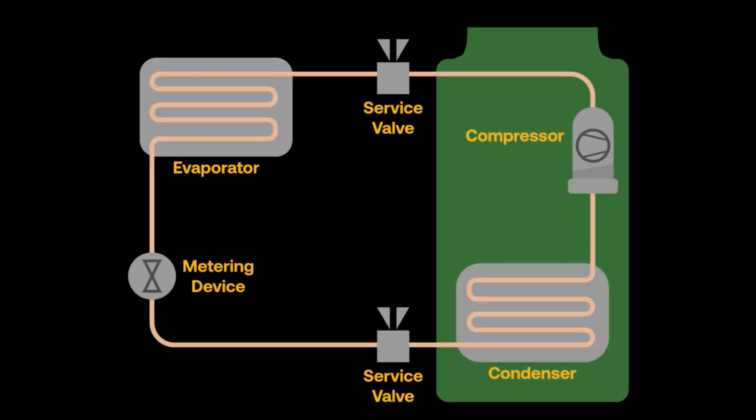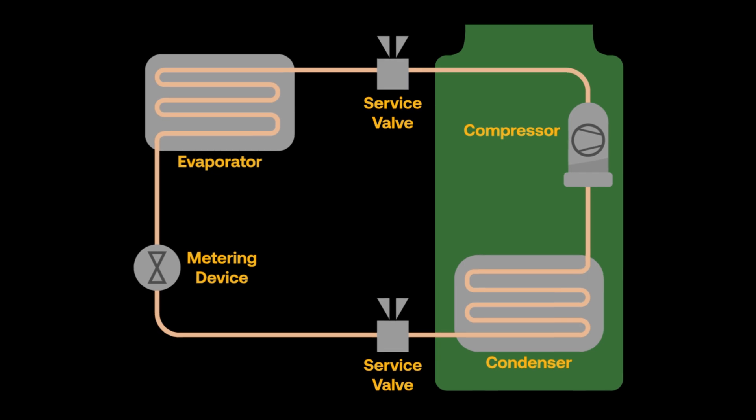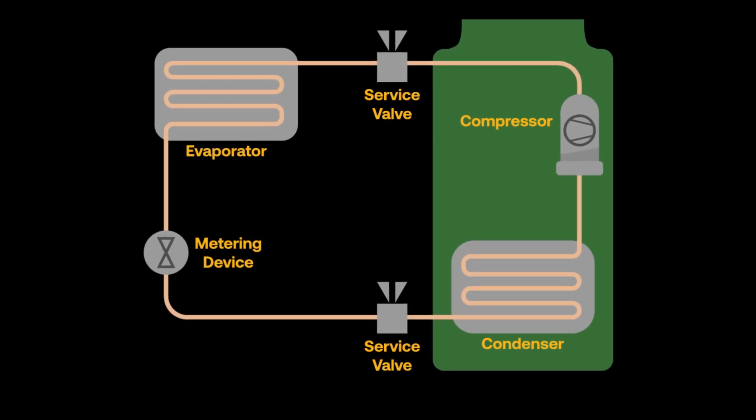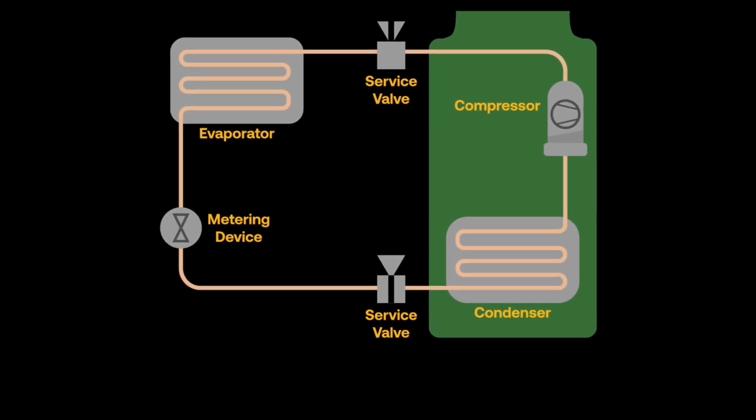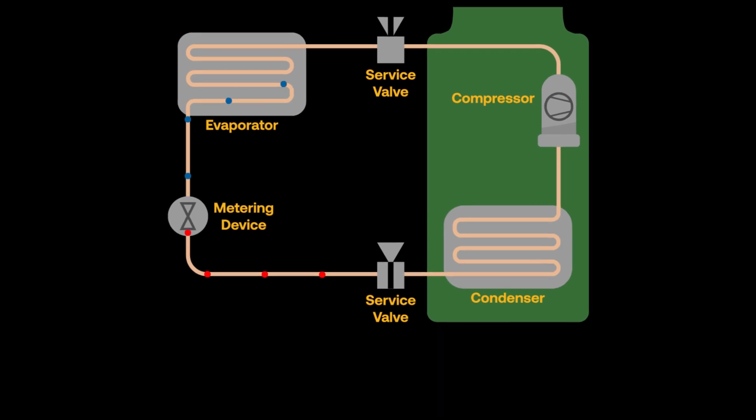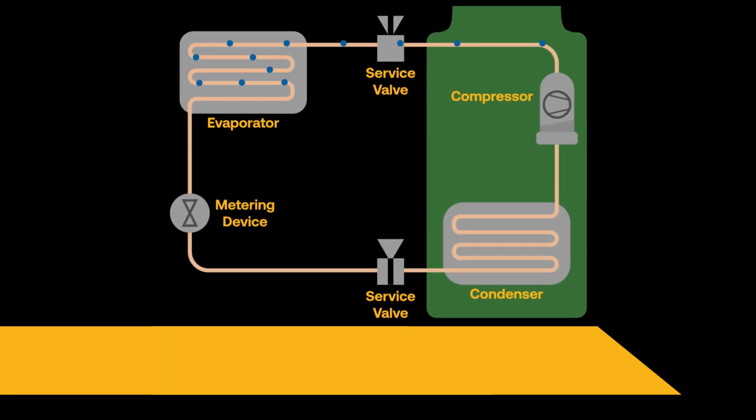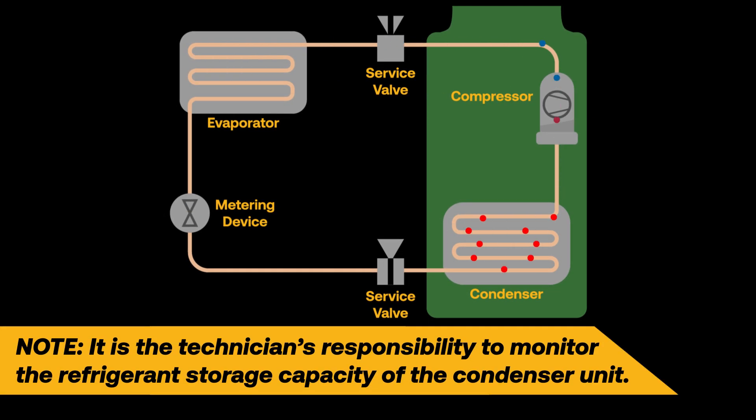In some instances, auxiliary recovery equipment may not be required at all. Modern VRF systems are equipped with a pump-down mode. This mode utilizes the system's own compressor to recover the refrigerant charge and store it in the condensing unit. This is particularly helpful for systems requiring repair to components beyond the condensing unit.